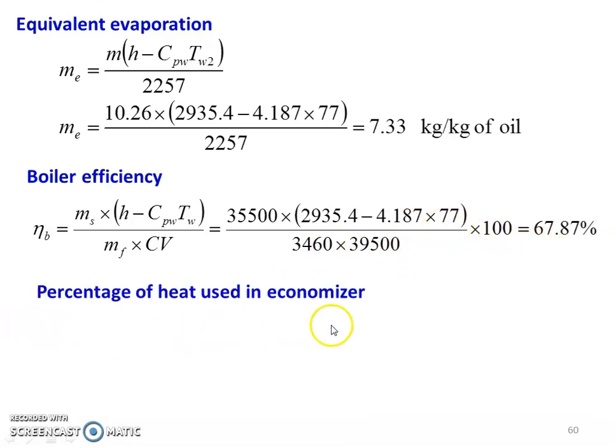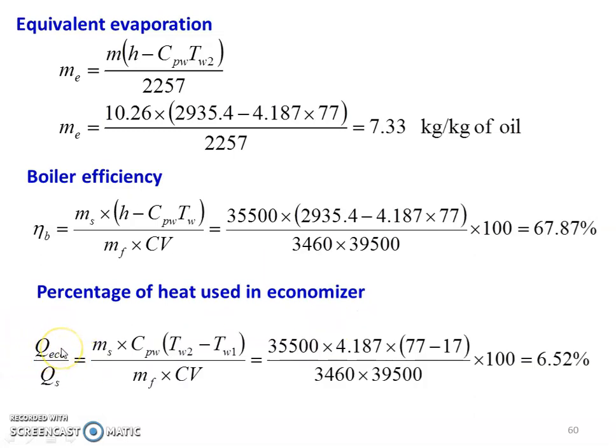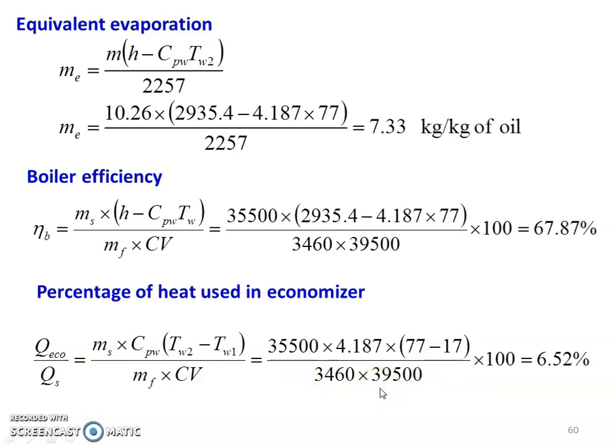Then, percentage of heat utilized in the economizer: heat utilized in the economizer equals mass of water (MS) into Cpw into (Tw2 minus Tw1), where Tw2 is the economizer outlet temperature and Tw1 is the economizer inlet temperature, divided by mass of fuel into calorific value. So, 35,500 into 4.187 into (77 minus 17) divided by 3,460 into 39,500 into 100 equals 6.52%. The answers to the question: equivalent evaporation is 7.33 kg per kg of oil, boiler efficiency is 67.87%, and percentage of heat utilized in the economizer is 6.52%.